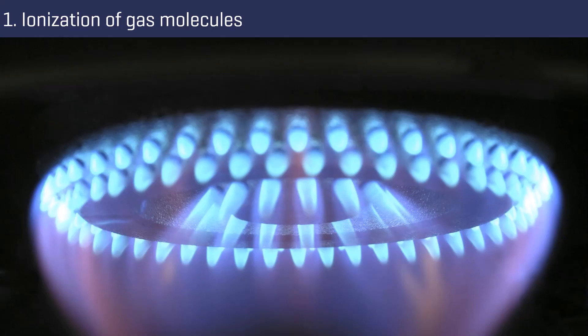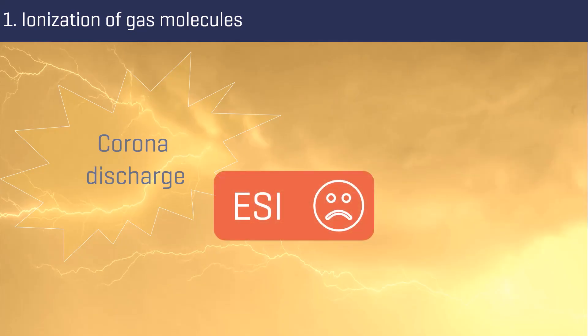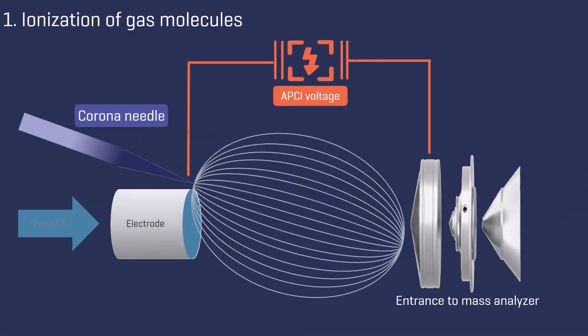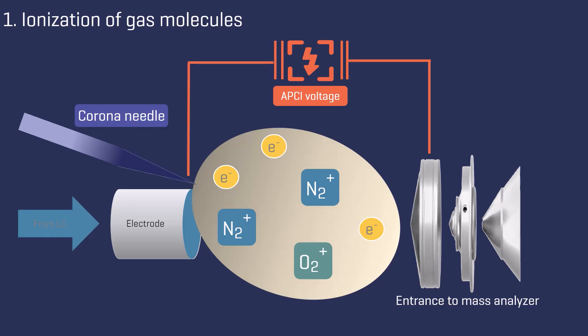We will now examine the ionization process in APCI step by step. The first step is the ionization of gas molecules and involves a corona discharge. While a corona discharge should be avoided when performing ESI, this phenomenon is an essential part of the APCI process. A field strength is applied to the tip of a corona needle, which separates electrons from the surrounding gas molecules in the ion source, and a gas plasma is formed containing ionized nitrogen and oxygen ions.